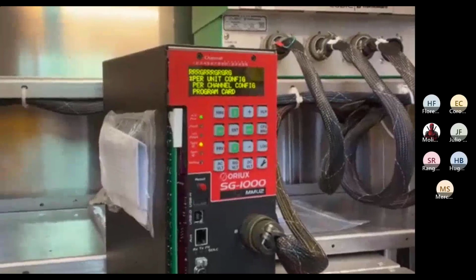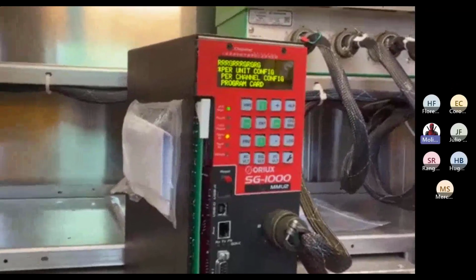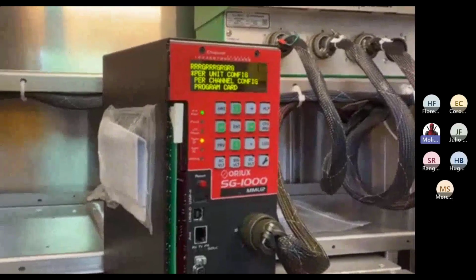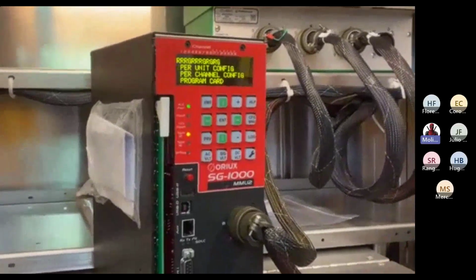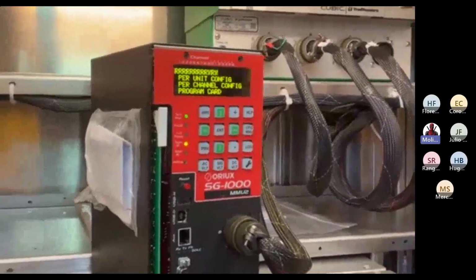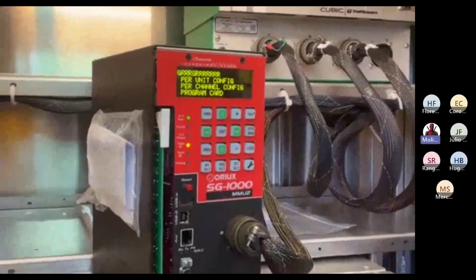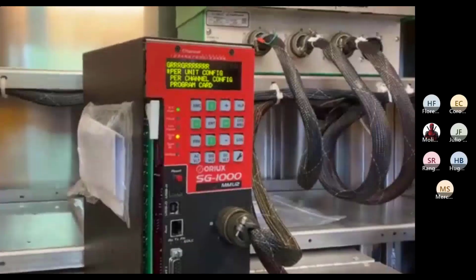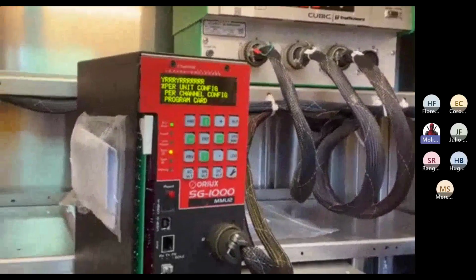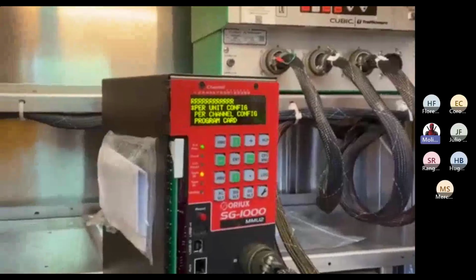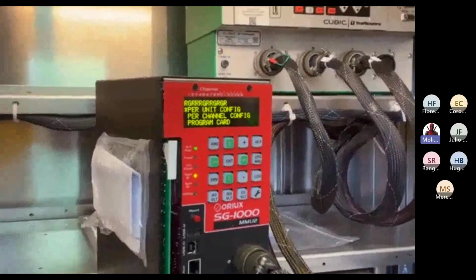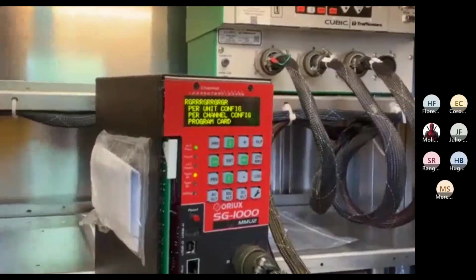So because you're not using the port 1, it's running as a type 12. You're right. So if you notice at the very top, see how there's nothing monitoring. Do you actually have channels 13 to 16 in there on your cabinet, on your back panel? Mm-hmm. So if you look on the very top of the display on the monitor, there's nothing there for those channels. So it's only picking up the 12 channel. It's not monitoring those extra 4 channels.